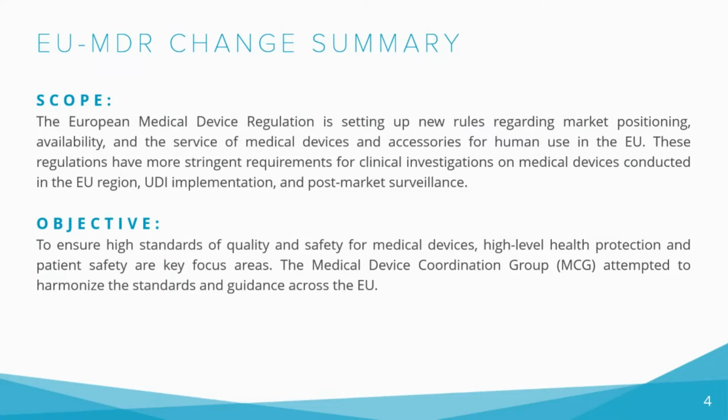But why MDD to MDR? It was needed because some blind spots, generally called weaknesses, were beginning to show up from organizations like CDMO, known as Contract Development and Manufacturing Organization. To understand this better, we may remember the scandal of the defective breast implants in France a few years ago. This was a part of recognizing structural weakness in the system and inconsistent interpretation of directives in different countries.